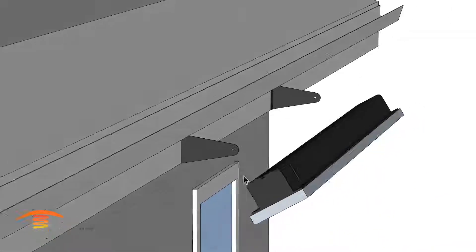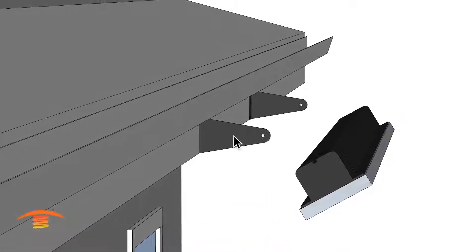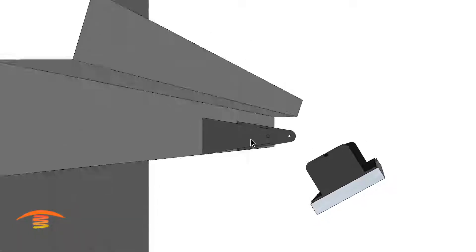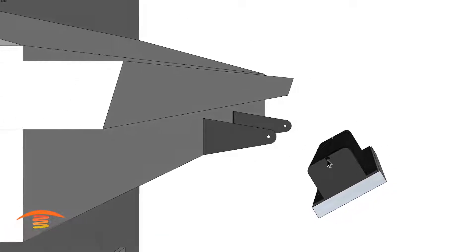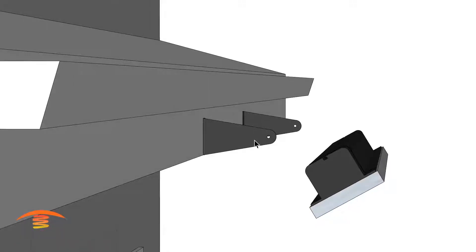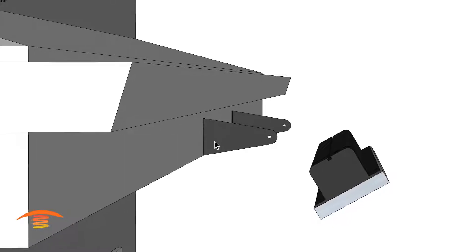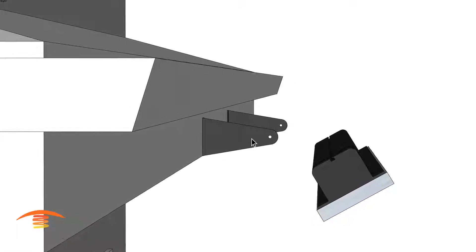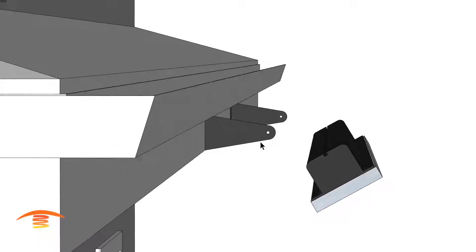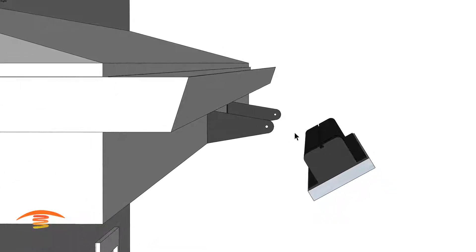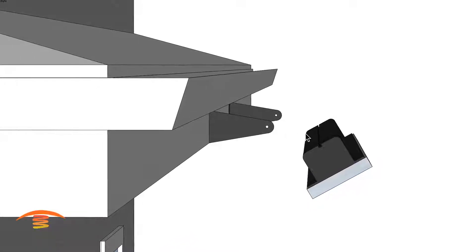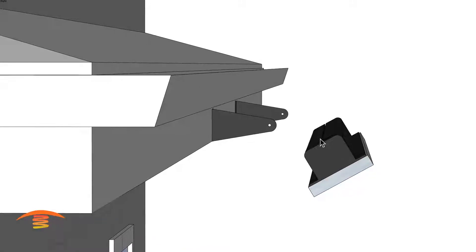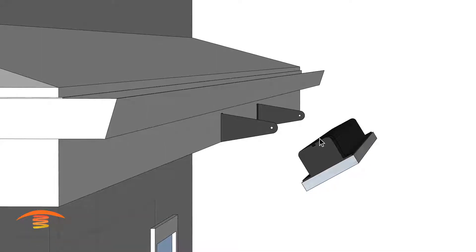But you can see I don't have it attached to the heater and that's because I don't have the extension mounting brackets modeled out here. But in any case, there is a two, a four, and a six inch extension. So that means that the bracket will look the same, it's just going to be two inches further, four inches and six inches. What I'm looking at here is approximately three inches of distance extension that I need. So we're going to have to go to the four inch extension. That's going to be true on the next example I give you as well.